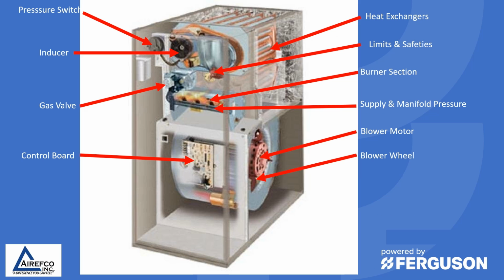Then the heat exchangers. They need to be examined on a regular basis, at least twice a year, to make sure that there are no holes or problems, cracking, rust, and corrosion that need to be addressed. The safety of the homeowners that have this furnace is in jeopardy here, and you as a technician need to make sure that the heat exchangers are in good shape.